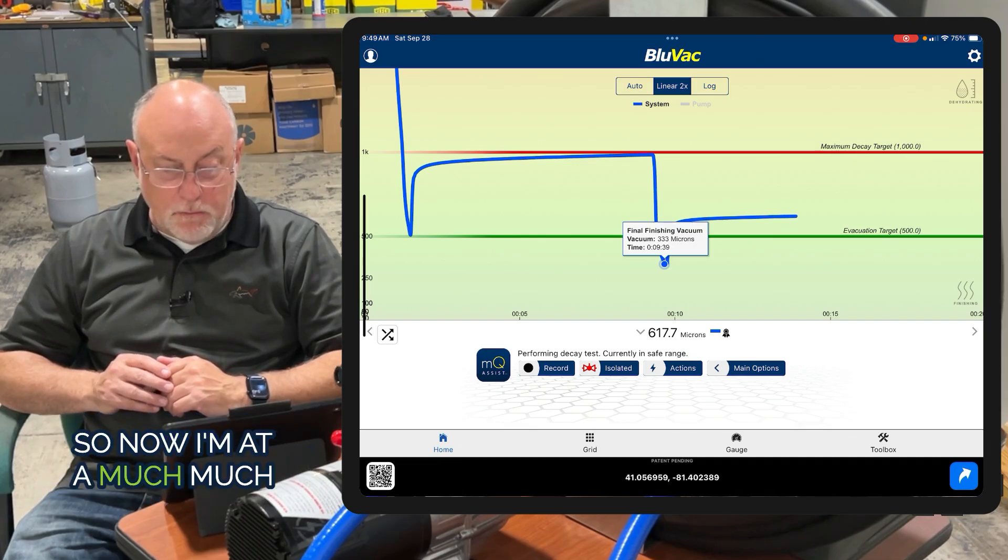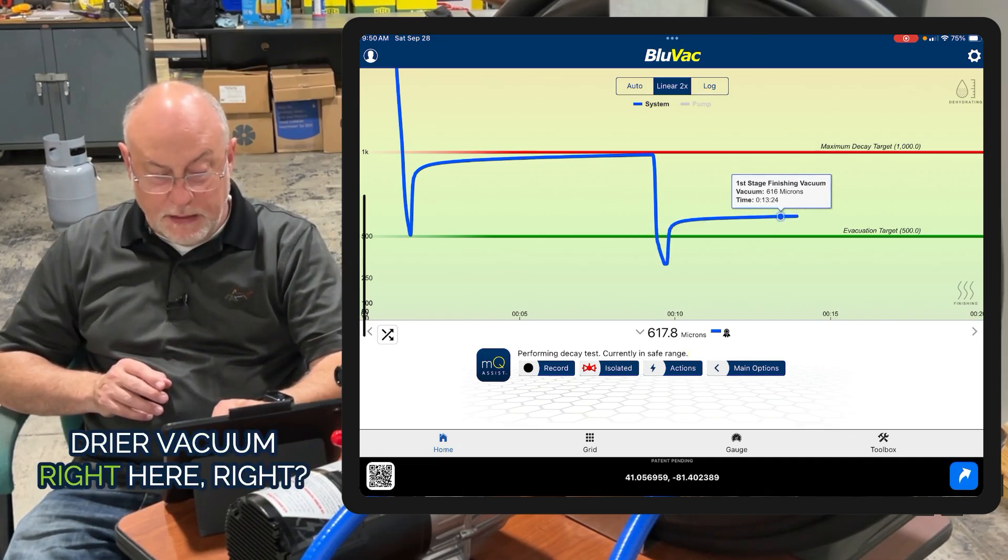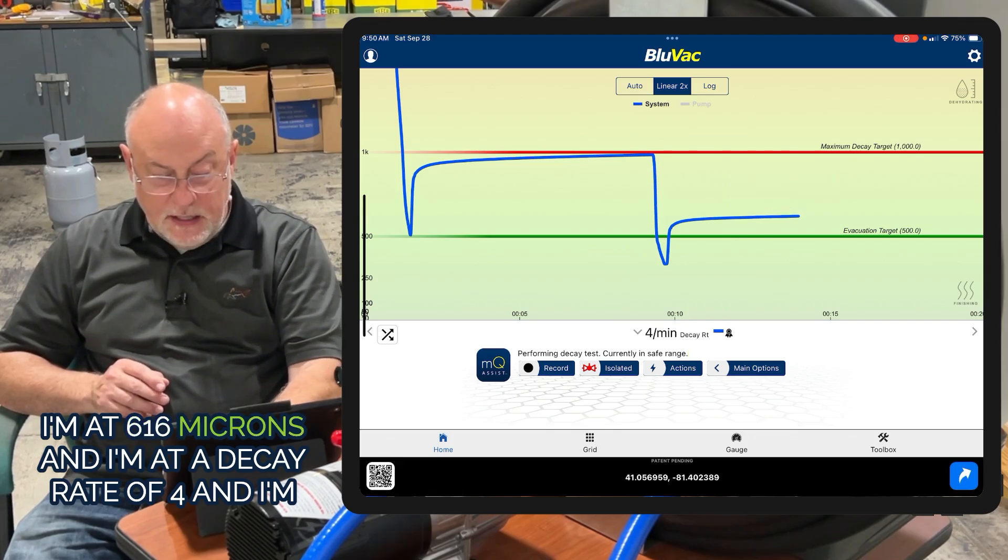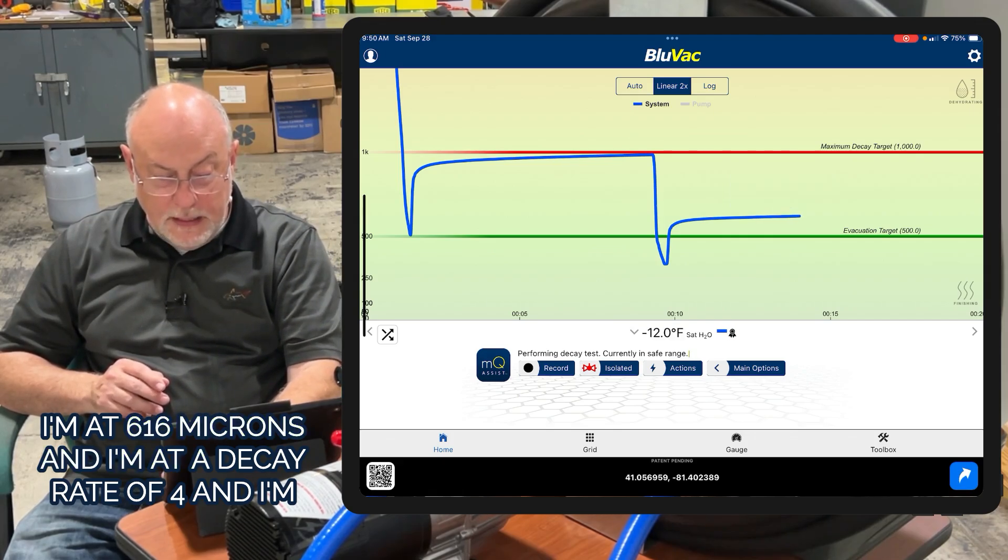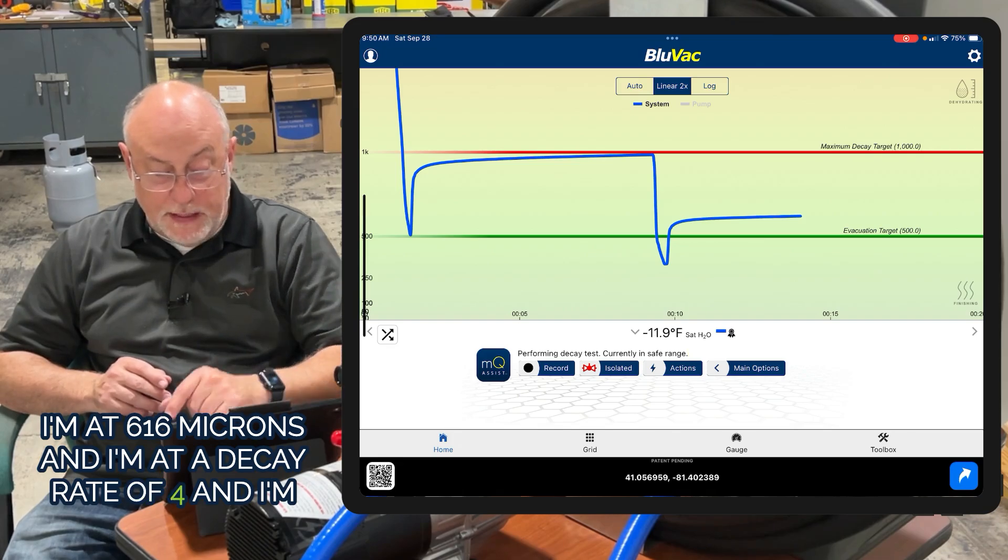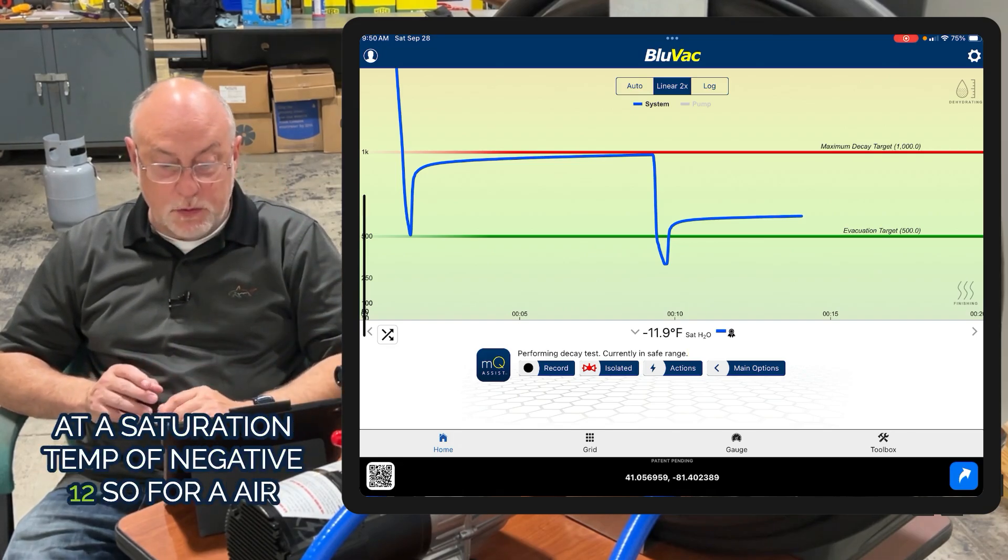Now I'm at a much drier vacuum. I'm at 616 microns with a decay rate of 4 microns per minute and a saturation temp of -12°F.